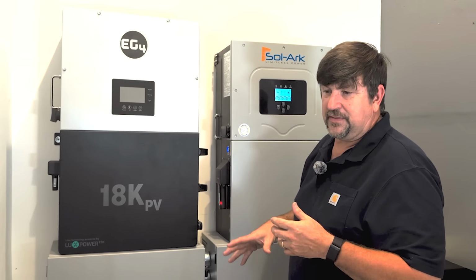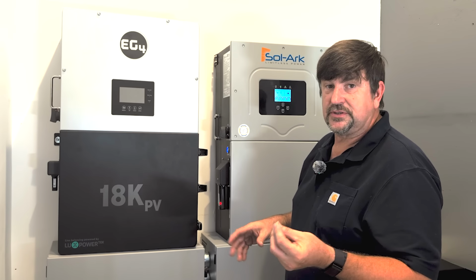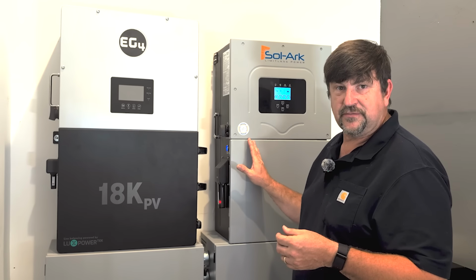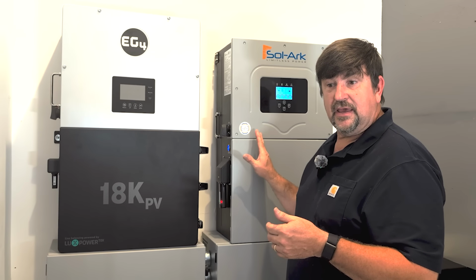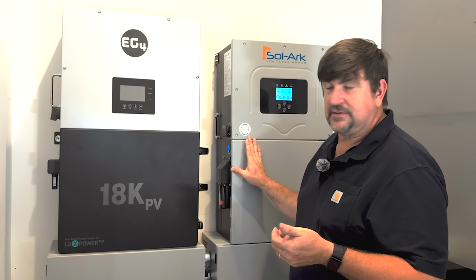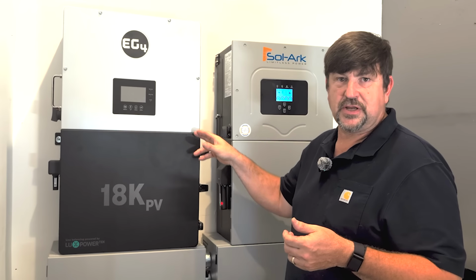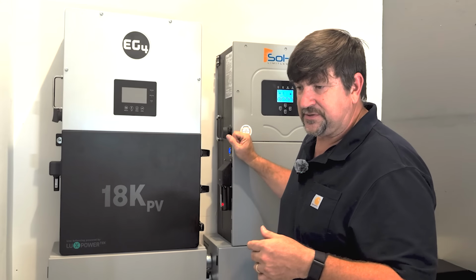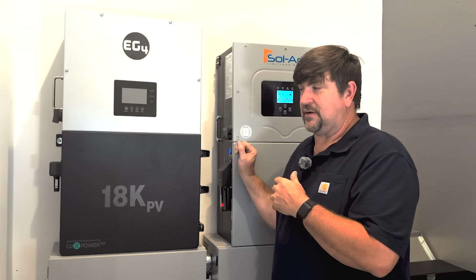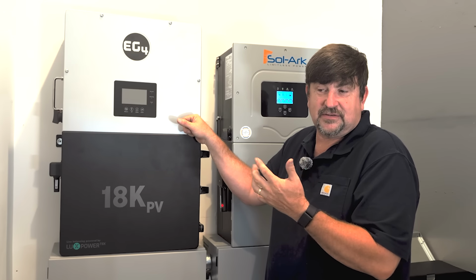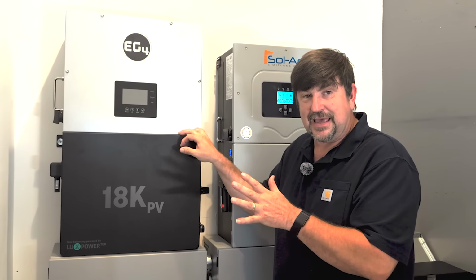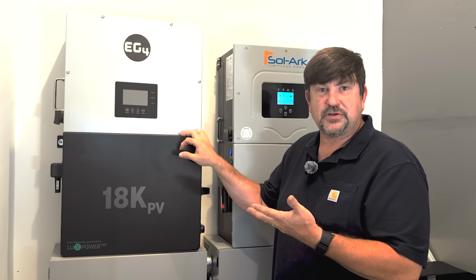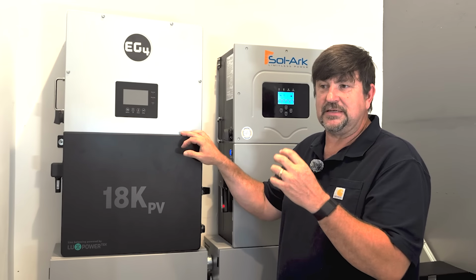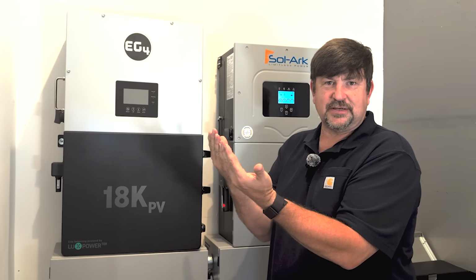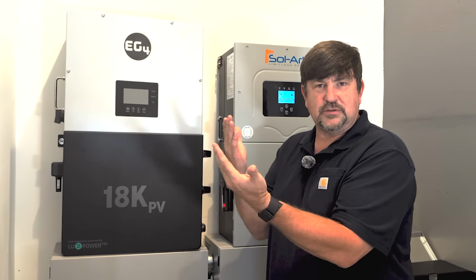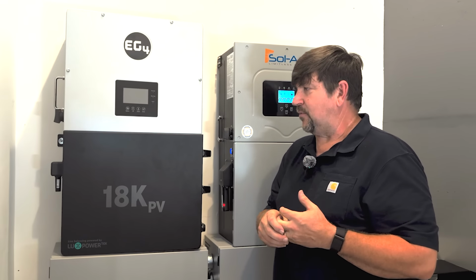They also don't specify the surge capacity of the machine for short-term surges. This one can go 24,000 watts for 10 seconds and 30,000 for 100 milliseconds. There's nothing reported on their spec sheet about surge capability. So even without soft starts, this can run a 4 to 5 ton HVAC unit — that one can't, unless somebody can prove me otherwise. Maybe it can, but they don't have their spec sheets up with the same detail, so it gets confusing comparing the two side by side. They're not very similar in many ways.